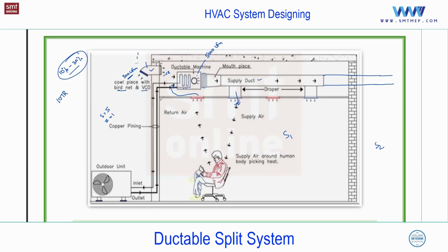VCD, in short, is a volume control damper. At this level, you can consider it like a valve in the pipe. In the pipe, as everyone knows, we use a mechanical valve to control the flow. Similarly, on the air side, we use a VCD, with a handle that you'll find opening or closing like a valve. In detail, we'll discuss at the time of air side what is VCD, what is manual VCD, what is motorized VCD, what the different dampers are, etc. At this level, I'm not explaining, because the point here is to explain what a ductable split is and how you are providing the fresh air.